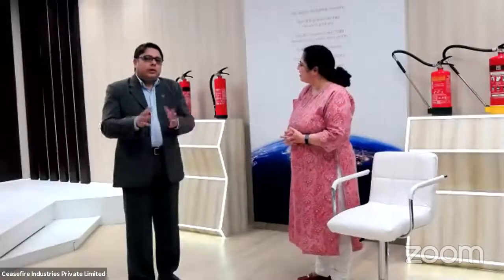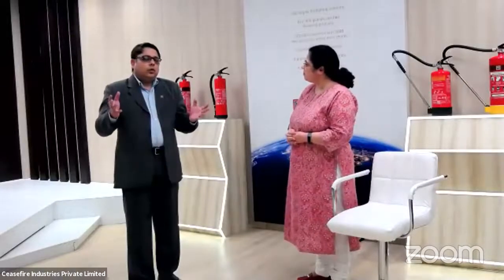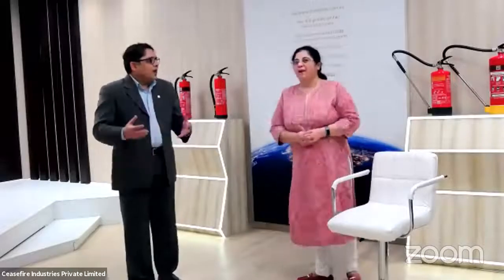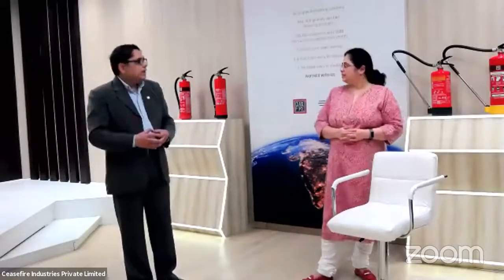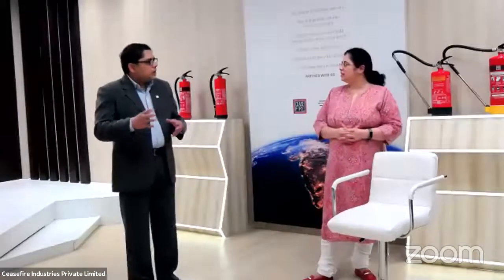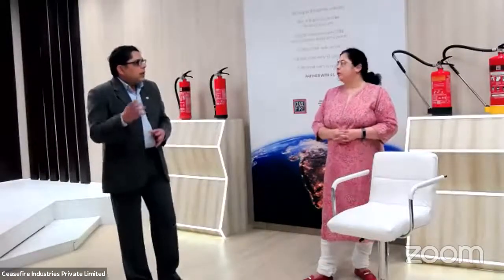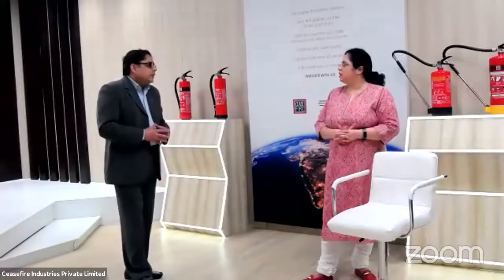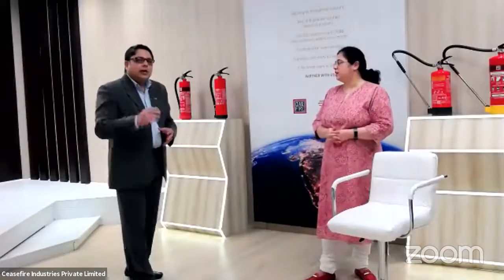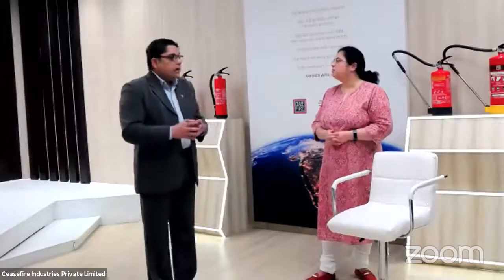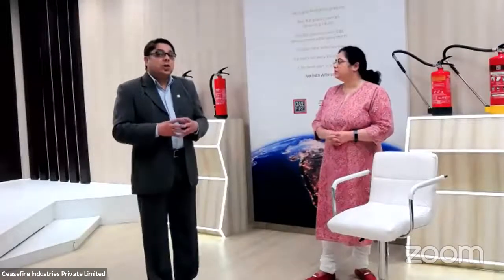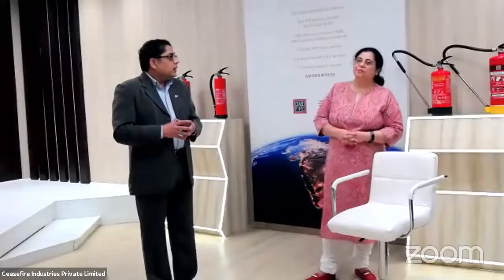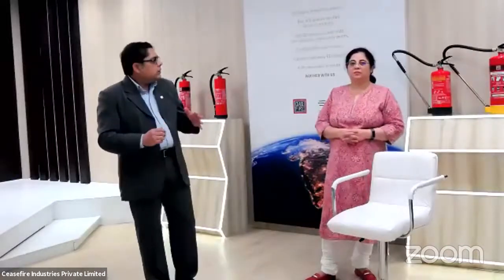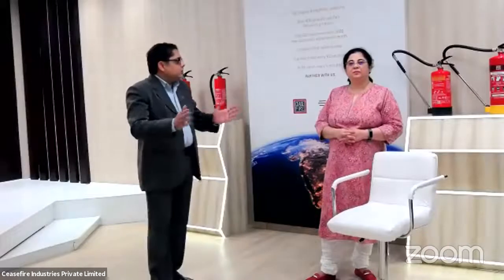Kaveri, we were just trying to demonstrate that the fire did not go out because the fuel had finished. We're trying to show you that there's still fuel inside, but the extinguishment was done by the agent. The agent we have inside is HFC 227. That is how it works: it eliminates all the heat, which is the most important component in fire, and with chemical interference it knocks out the fire quite early in the stages. So one, you are knocked down, and the other is that you have no reignition.